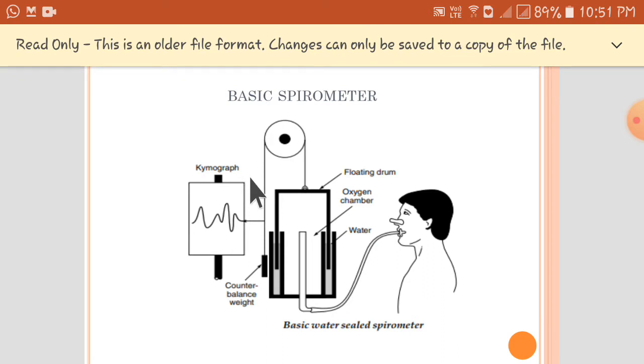A kymograph is a device that draws a graphical representation of spatial position. That is, the kymograph consists of a revolving drum wrapped with a sheet of paper on which a stylus moves back and forth. This is the stylus. The movement of the stylus will be proportional to the movement of the inverted counterweighted bell, and that in turn is proportional to the volume of the air in the chamber. That is, as the patient breathes, the volume changes. Proportional to that, the inverted counterweighted bell moves vertically, and that vertical movement is drawn by the stylus on the paper of the kymograph. Thus, the graphical representation is obtained. So, that was the working of a basic spirometer.